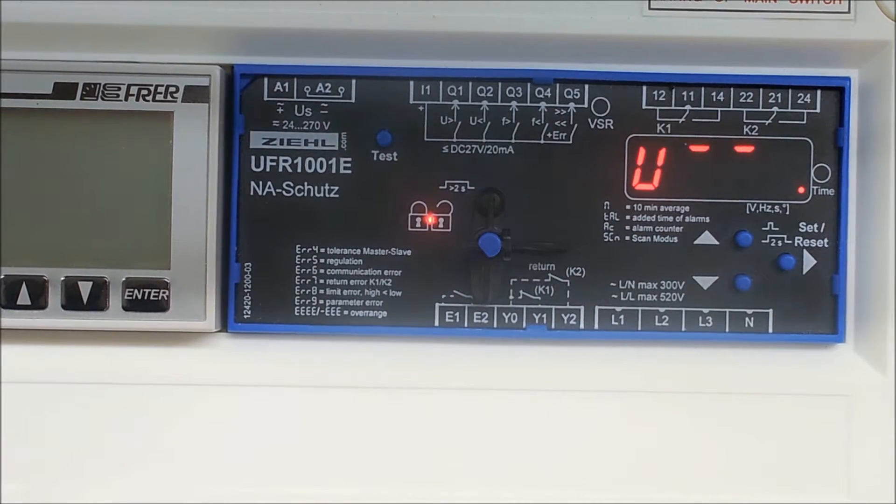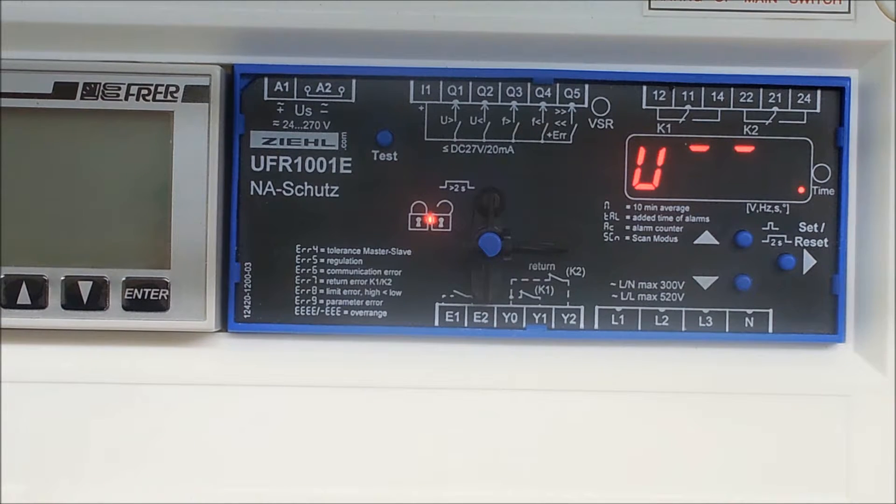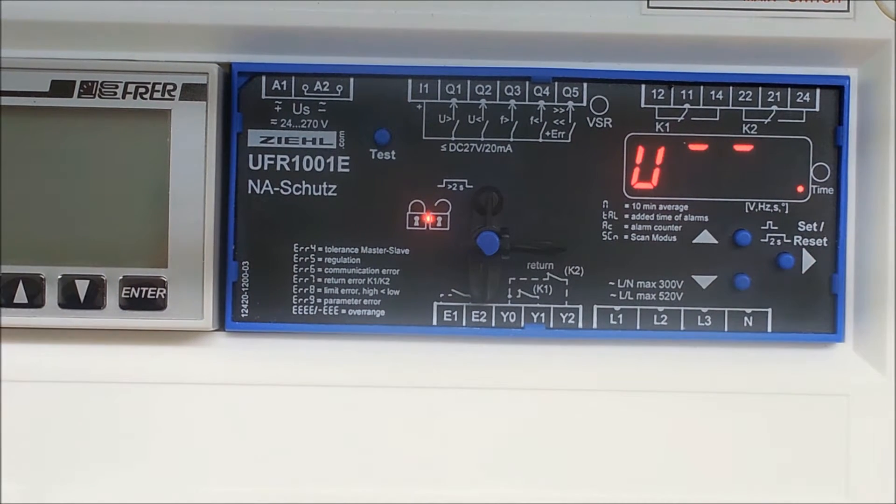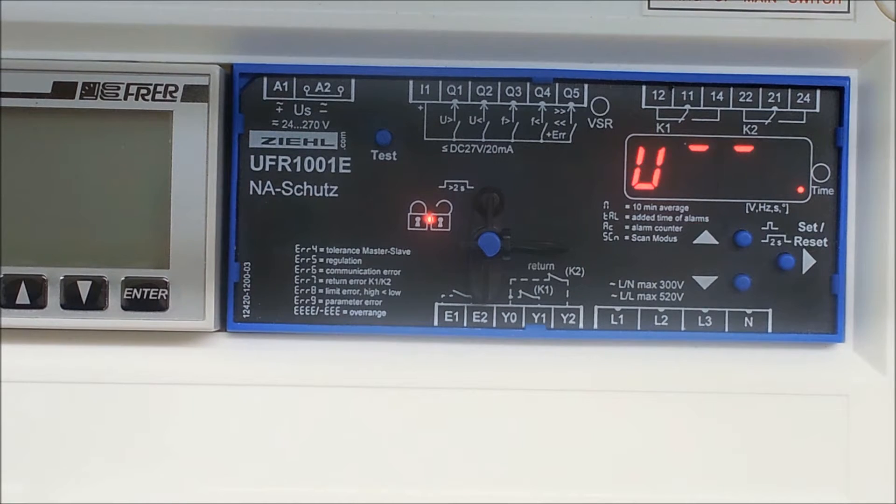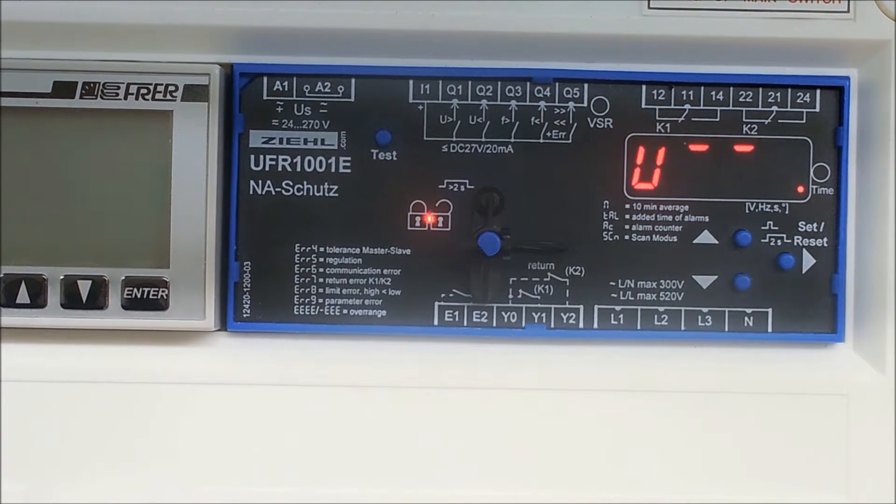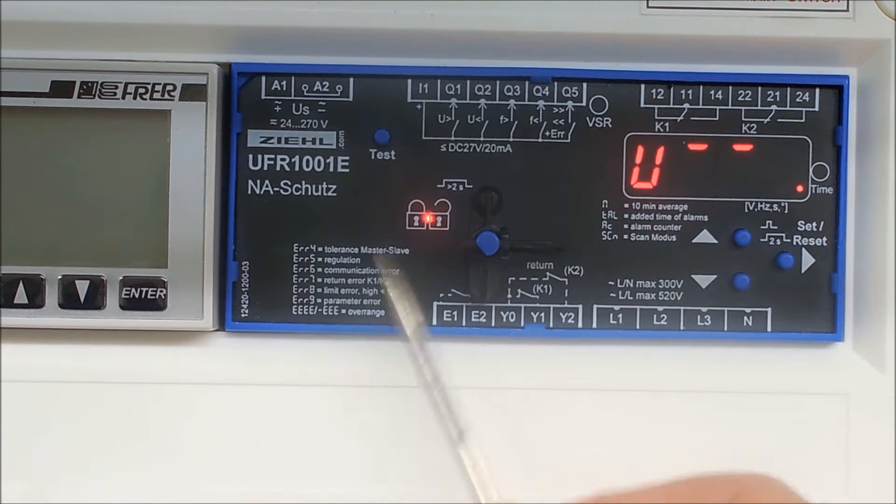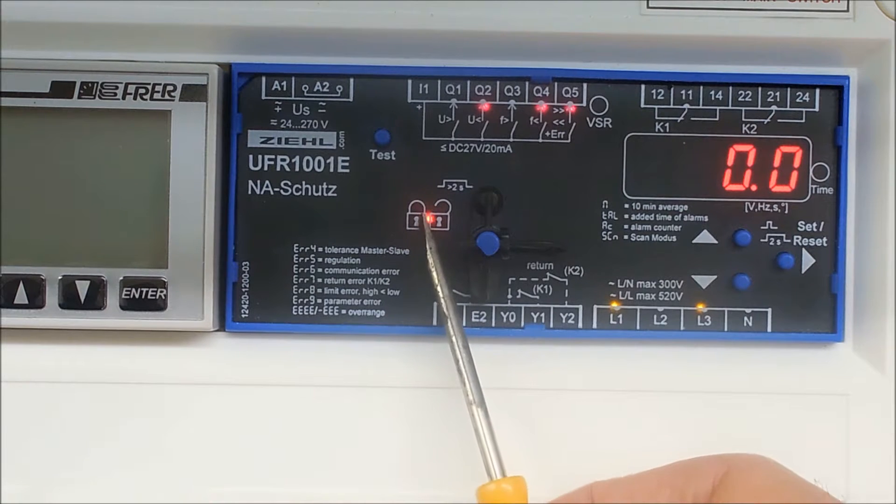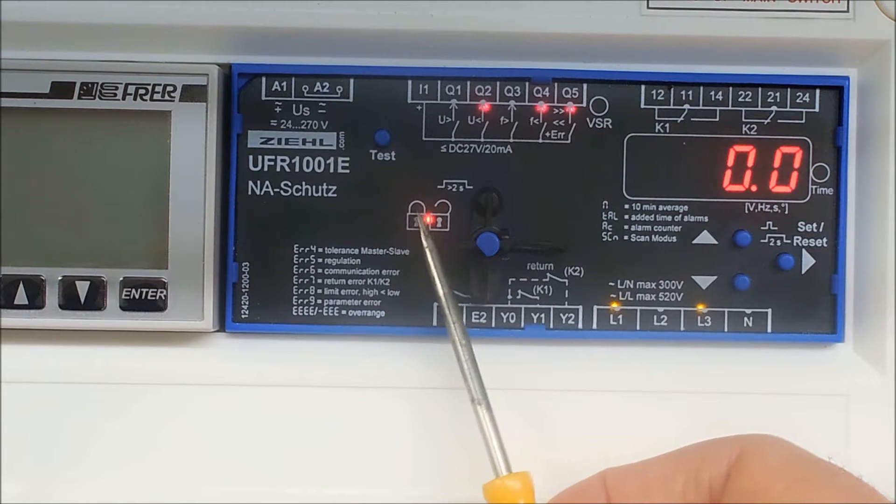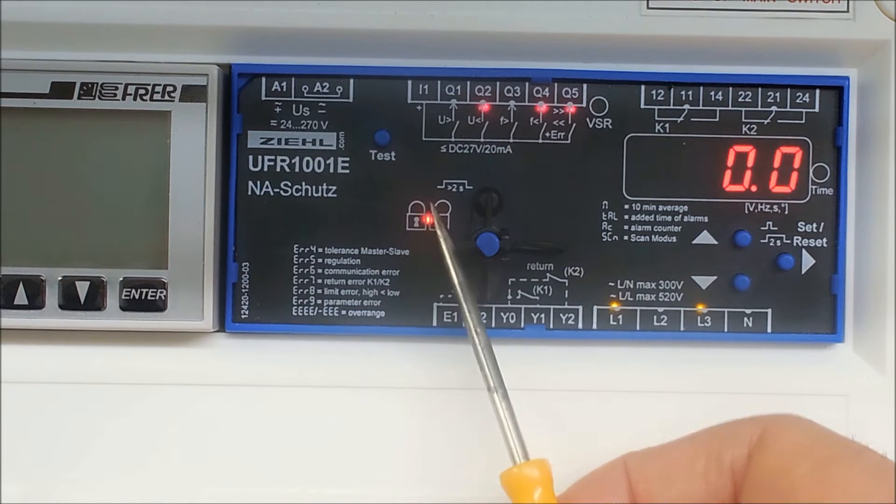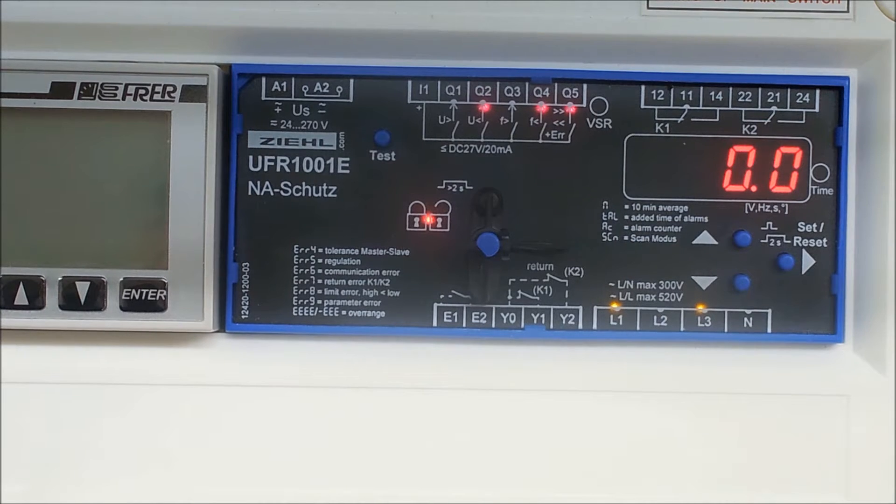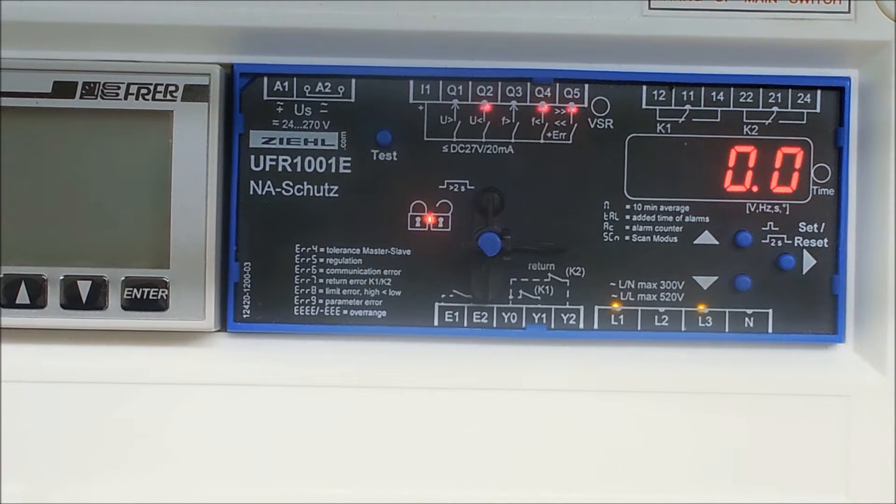This is the UFR 1001E Ziehl G59/3 compliant relay. This mode you have it here set up in is in the monitoring mode as if it would be after it had been commissioned and installed. You can tell this because you have a red LED here which indicates under this padlock symbol that the unit is locked. Which means you cannot alternate the values but you can read the values of course.